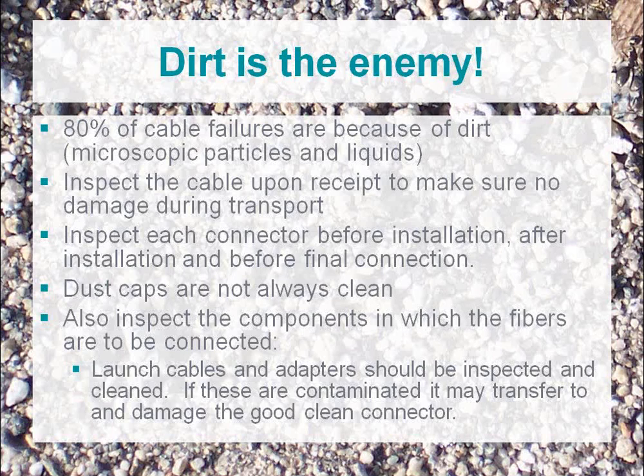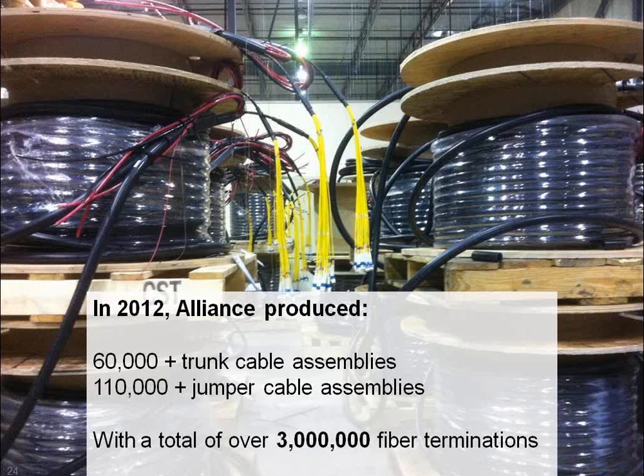It is important to inspect the cable upon receipt to make sure no damage has happened during transport. It's important to inspect every connector prior to installation. It's important to inspect the ports that the fibers are being connected to as well. People think that if you're working with a clean fiber, you put the dust cap on it and you'll have no issues. But dust caps, because of how they're manufactured, do introduce contaminants. Dust caps are only there to protect the fiber during transport and during installation. So it's always wise to inspect the fiber every time you remove a dust cap. And it's always important to check testing gear, launch cables and adapters prior to doing any fiber testing or inspection. Because if these are damaged or contaminated, they will contaminate and damage the good fibers.